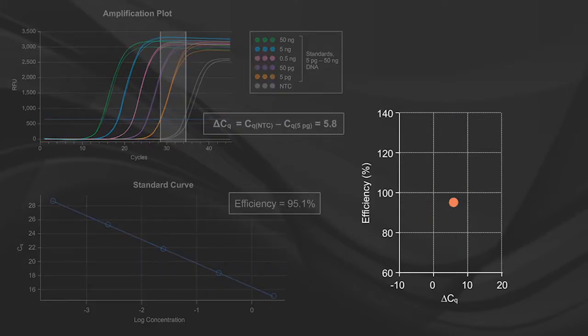By providing guidelines around the typically accepted values for these parameters, for example, a 90-110% efficiency and a delta cq of 3 or greater, this created a graphical visual referred to as dots and boxes. However, it didn't quite capture all of the relevant details of each run.